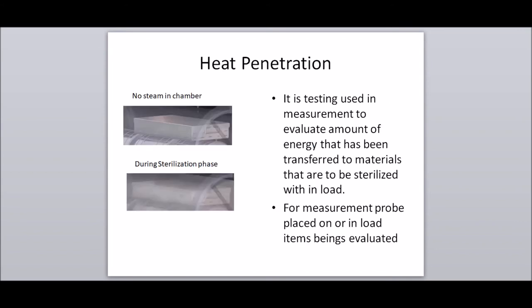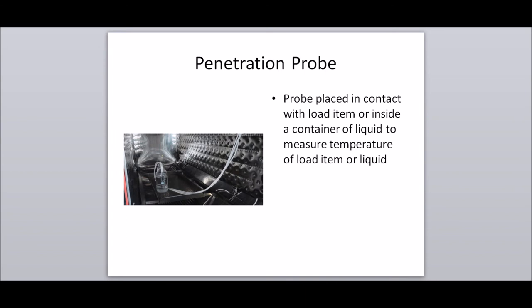Heat penetration: testing used to evaluate the amount of energy transferred to materials to be sterilized within the load. For measurement, a probe is placed on or in the load items being evaluated. Penetration probe: a probe placed in contact with a load item or inside a container of liquid to measure the temperature of the load item or liquid.